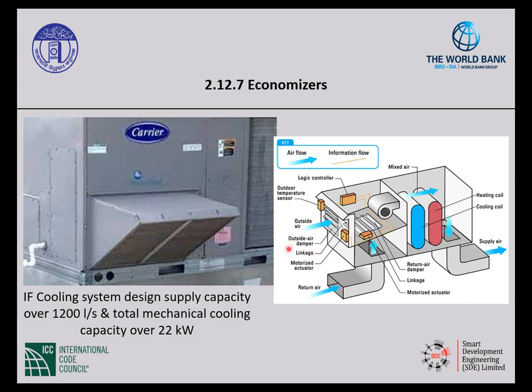So an economizer brings in the outside air, runs it across the heat exchanger, kind of like an ERV, and distributes the air in, but it also has the ability to shut the cooling portion off, that refrigerant flow, and just bring in that outside air and run it across there instead. There are sensors and things that are built into these economizers to do that. Once the air gets up to a certain point, or you could have humidity levels on there, there are different things that you can put on these to shut off that outside air and go back to your mechanical system. So this is an economizer.